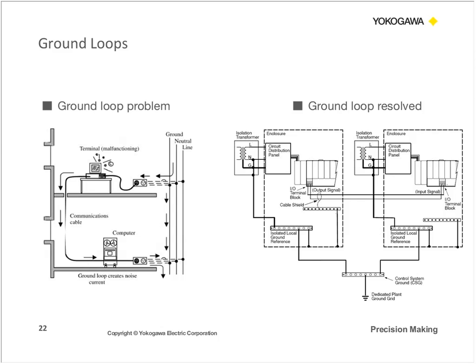So as you can see, even though we have an I/O signal from enclosure 1 to enclosure 2, this does not result in a ground loop. And this is really because each of them has an isolated return. So what that means is the output and the input from both sides are not referenced to a different ground. But let's say, and this commonly occurs in many facilities, it's not practical to connect everything to one local ground. In those situations, a common solution is to implement not only isolation, but signal conditioning as well. And we'll take a look at the different types of isolators and signal conditioners you can use to solve those problems in the next section. But for now, let's move on to our next problem.